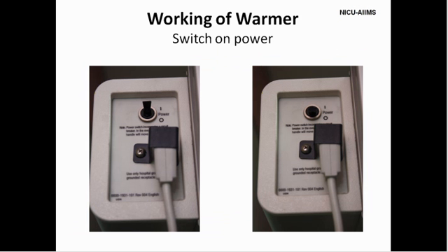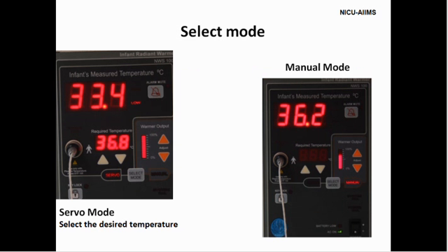The next part of our discussion deals with the steps of preparation of the radiant warmer. The first step is to connect the unit to the mains and finally switch it on. Then select the mode, which could be either servo mode or manual mode, from the control panel. Increase the heater output to 100% if you have selected the manual mode to allow pre-warming of the bed covered with linen.